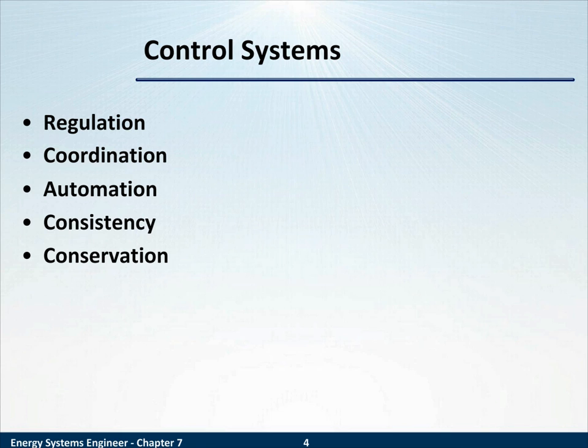Control systems can automate, but be careful. They will automate whatever they did before. They cannot make judgments or split-second complex decisions with new data. So if you have a process that's not working and you have it automated, it'll not work every time. The next thing a control system offers is consistency. Because of automation, the control system can measure and make changes to obtain consistency in your process. Again, it can't make a judgment call, so if it's making something bad, it'll make it consistently bad.